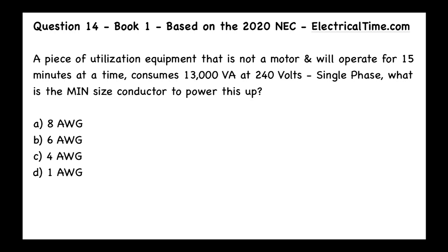Question 14, book number one, based on the 2020 NEC from electricaltime.com. A piece of utilization equipment that is not a motor and will operate for 15 minutes at a time consumes 13,000 VA at 240 volts single phase. What is the minimum size conductor to power this up? The answer to this question is B, which is 6 AWG.